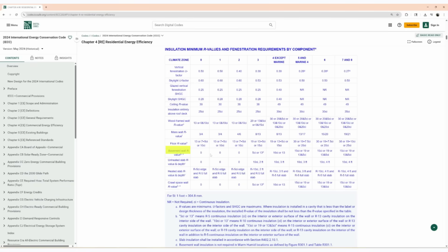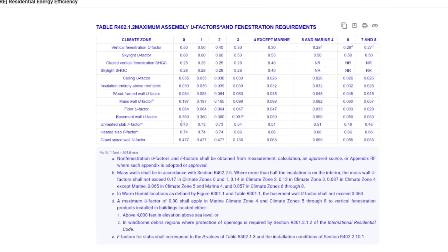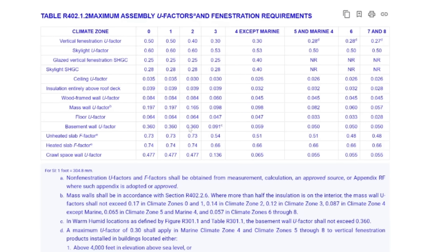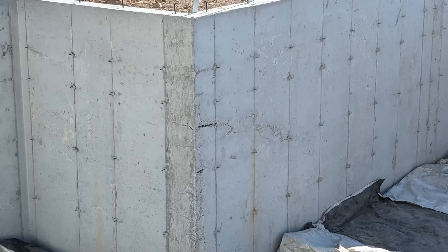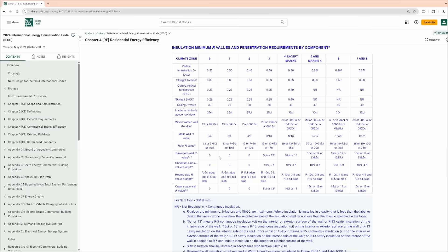If we take a look at the required basement wall R-value, we see that in climate zones 0, 1, and 2, your basement walls aren't even required to be insulated, but they do have to meet a maximum U-factor of U.36. This is just the inverse of R-value. So basically, if you construct your basement walls out of concrete, it'll meet this requirement — we actually get a lot of cooling benefits from having that wall thermally coupled to the ground. However, as we get into climate zones 3 through 8, there are clear R-value requirements that have to be met in order to meet code.